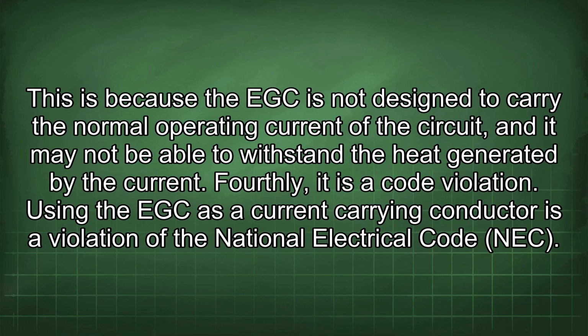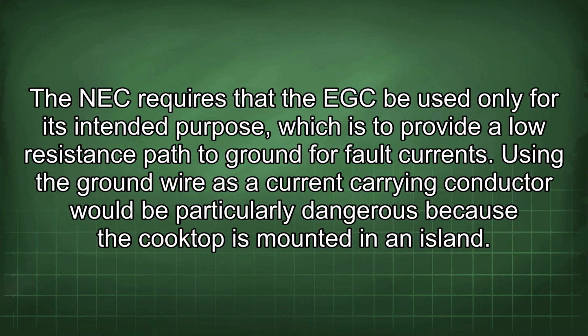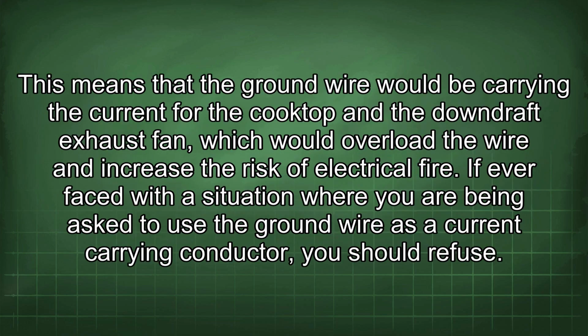Fourthly, it is a code violation. Using the EGC as a current carrying conductor is a violation of the National Electrical Code (NEC). The NEC requires that the EGC be used only for its intended purpose, which is to provide a low resistance path to ground for fault currents. Using the ground wire as a current carrying conductor would be particularly dangerous because the cooktop is mounted in an island. This means that the ground wire would be carrying the current for the cooktop and the downdraft exhaust fan, which would overload the wire and increase the risk of electrical fire.